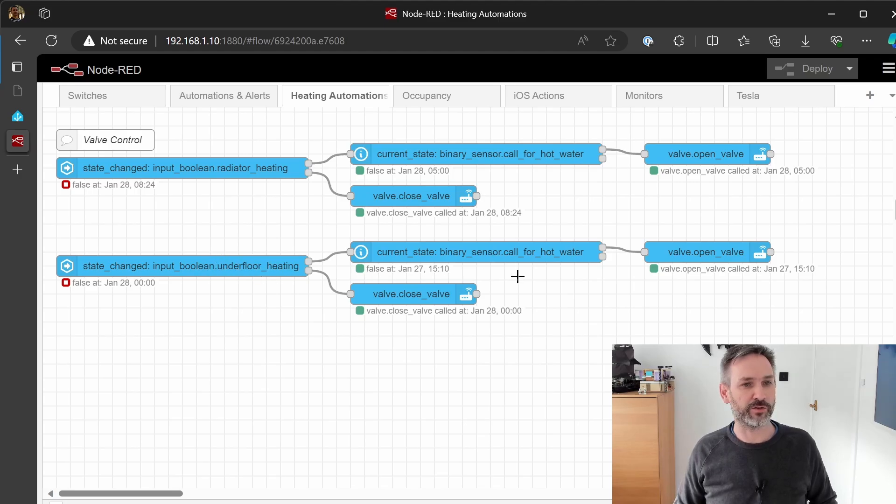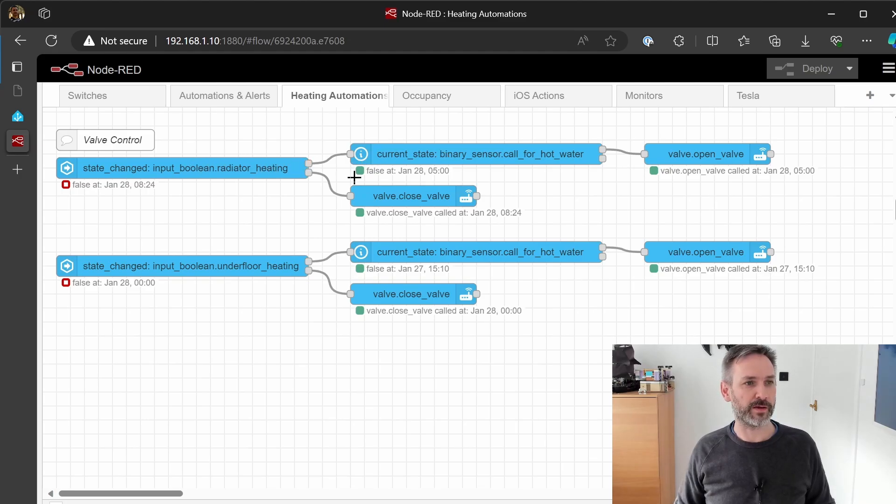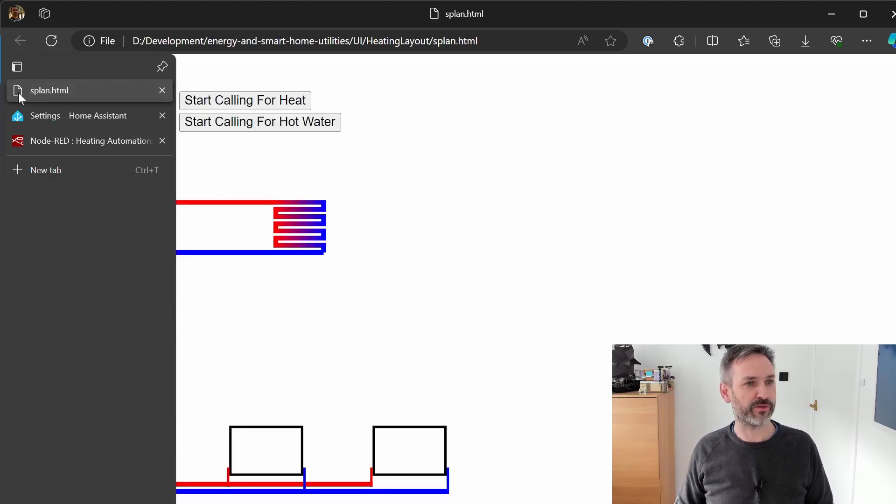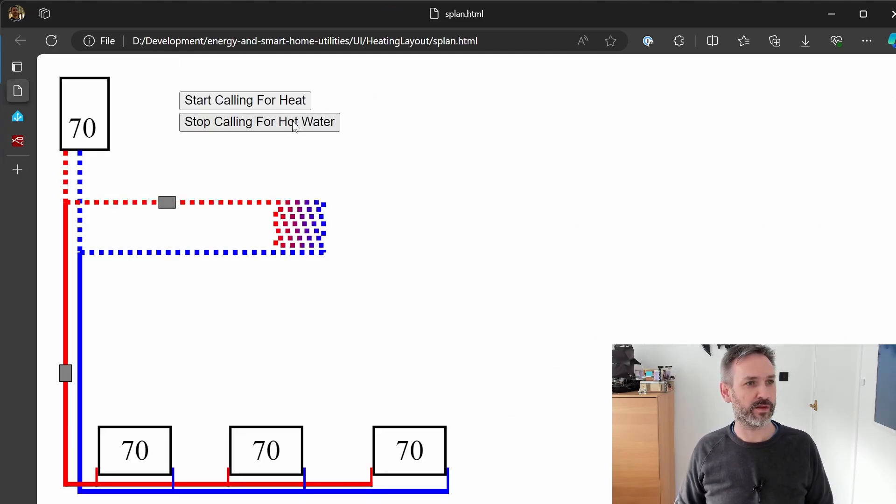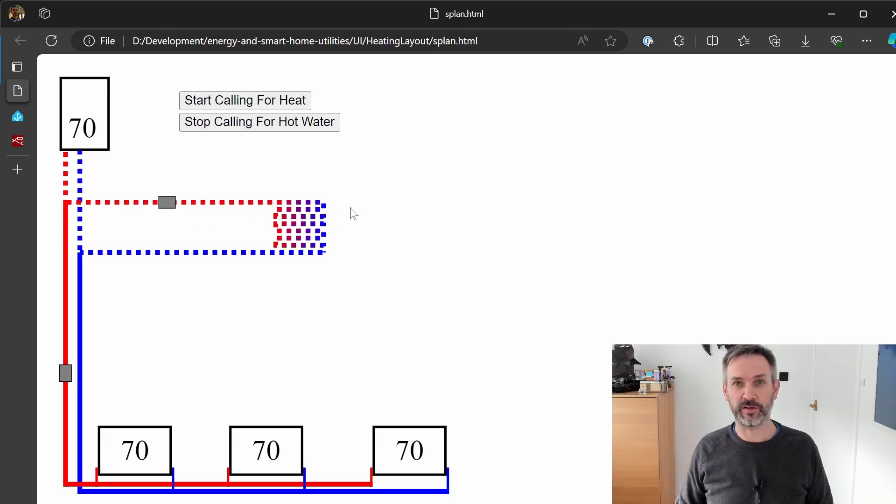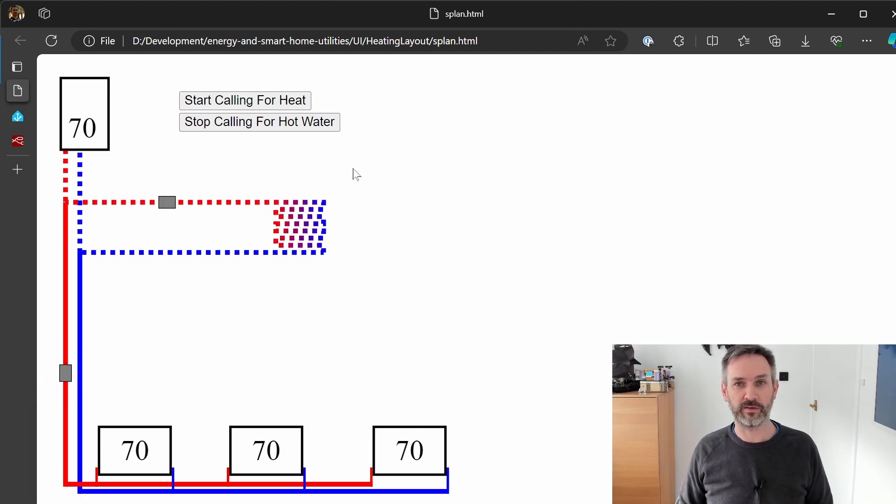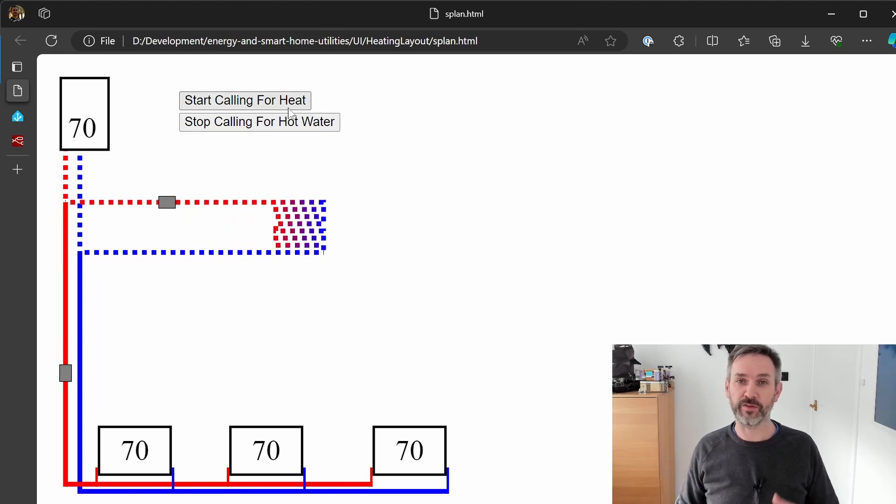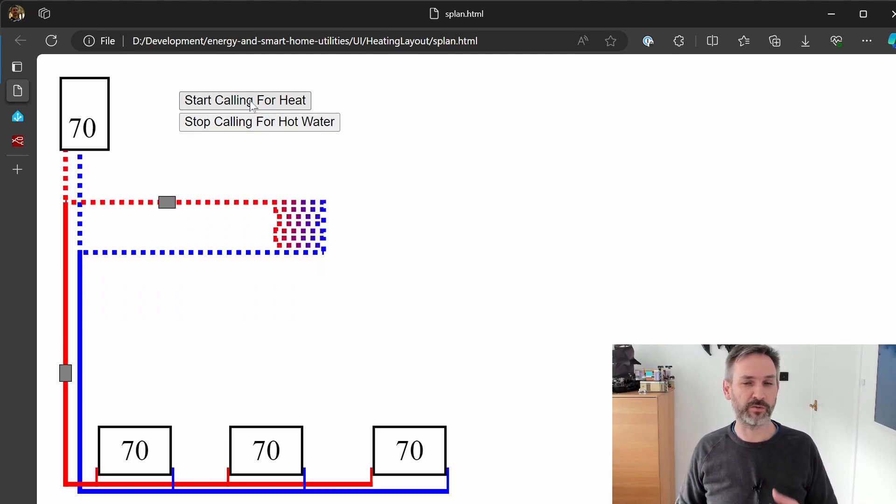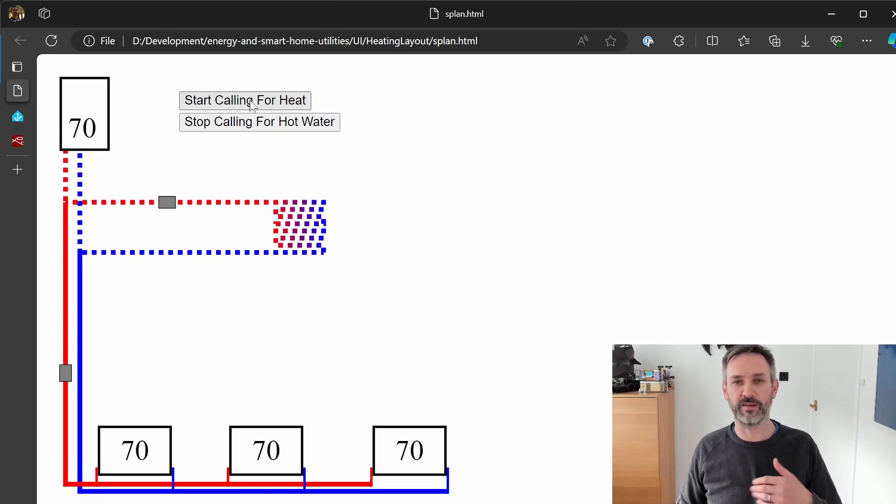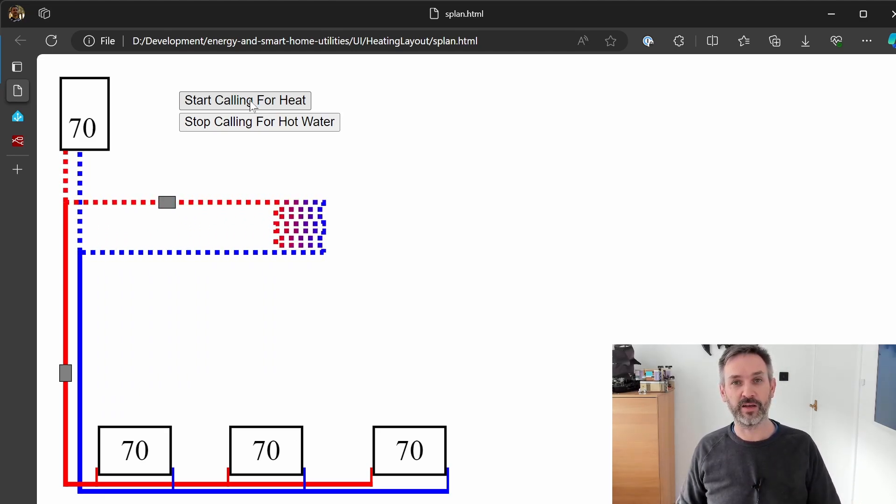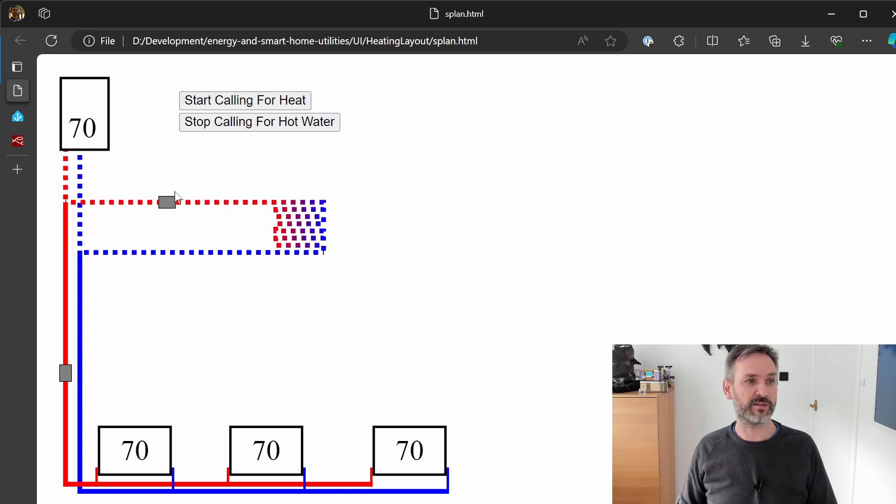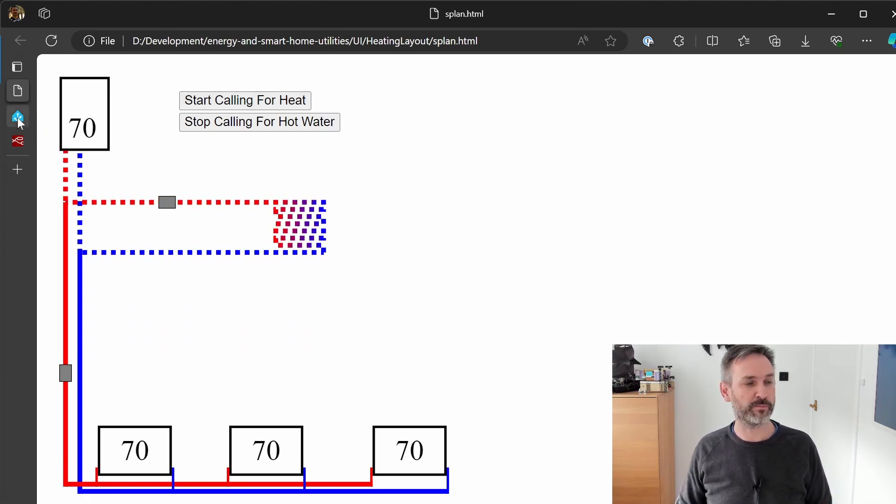What they will do when they're turned on is they will typically open the valve which will then engage the boiler and start the water flowing around. Same for the underfloor heating, it's the same process but where I've got to be careful is when the heating is on. If you remember from the diagram, if the hot water is currently on we do not want to open the heating valve so even if there is a call for heat coming from the thermostat I don't want to open the valve whilst the hot water valve is open.